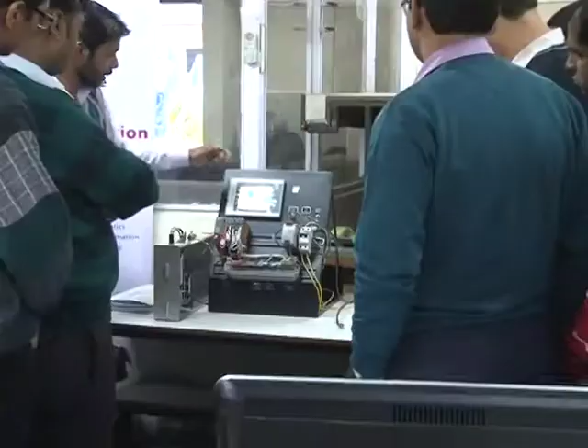If you put it in remote, all the controls will go to the Siemens part. Both the Siemens and B&R parts are currently communicating on Modbus TCP, through a simple Ethernet communication cable. One cable connects to the switch, and the second cable goes to the Siemens PLC. They transfer registers between the Siemens PLC and the B&R PLC.